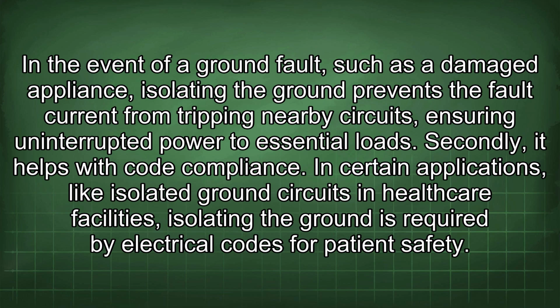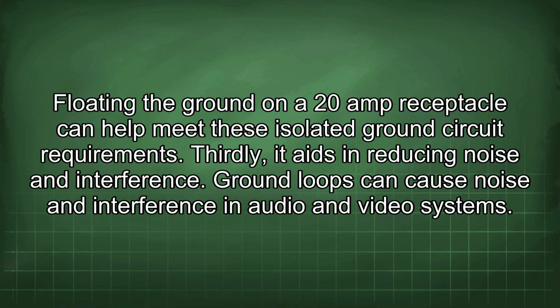Secondly, it helps with code compliance. In certain applications, like isolated ground circuits in healthcare facilities, isolating the ground is required by electrical codes for patient safety. Floating the ground on a 20-amp receptacle can help meet these isolated ground circuit requirements.